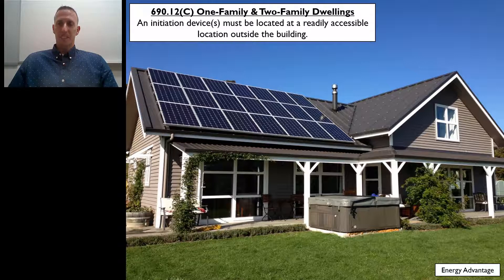In 690.12(C) of the 2017 National Electrical Code, it focuses on the rapid shutdown requirements related to one-family and two-family dwellings. It states that the initiation device must be located at a readily accessible location outside the building.